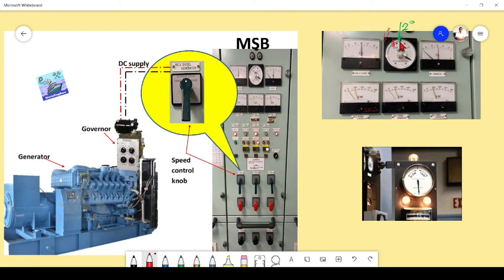That is the best place to close the breaker, then there will be no heavy circulating current. To achieve the exact contact making time at the time of this 12 o'clock position, it is recommended to close or initiate the breaker operation at 11 o'clock position. When the pointer comes here, we can operate the breaker switch. This is the breaker switch.